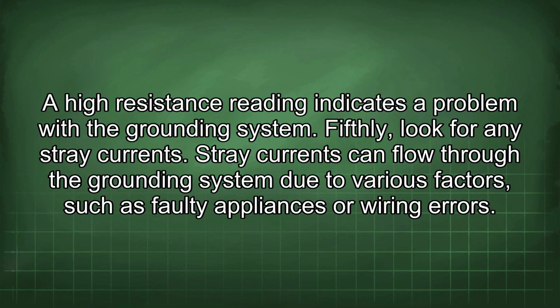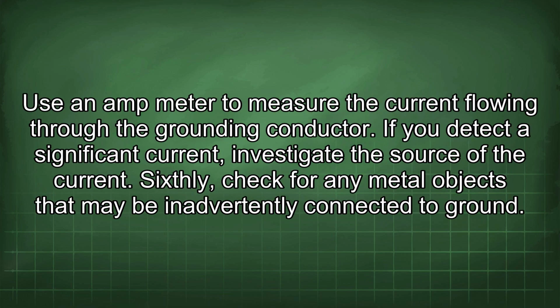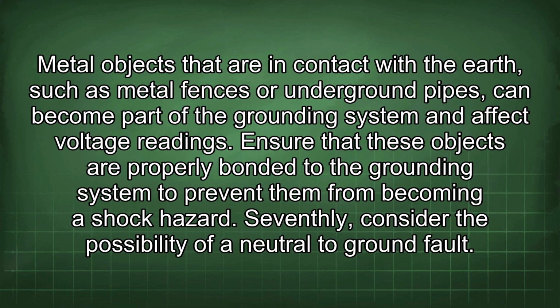Fifthly, look for any stray currents. Stray currents can flow through the grounding system due to various factors, such as faulty appliances or wiring errors. Use an ammeter to measure the current flowing through the grounding conductor. If you detect a significant current, investigate the source of the current. Sixthly, check for any metal objects that may be inadvertently connected to ground. Metal objects that are in contact with the earth, such as metal fences or underground pipes, can become part of the grounding system and affect voltage readings. Ensure that these objects are properly bonded to the grounding system to prevent them from becoming a shock hazard.